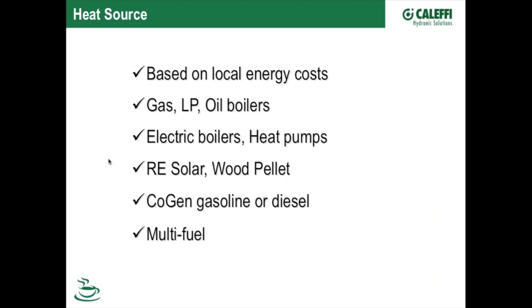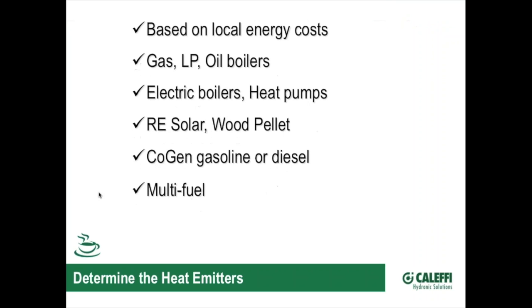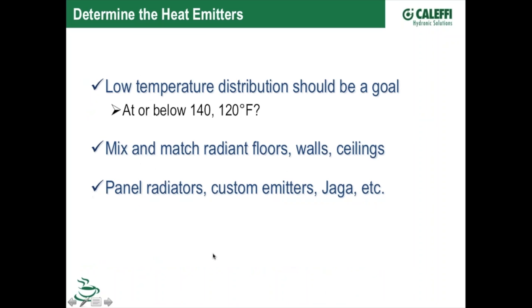You can compare the cost of operation for different types of fuel sources. There are calculators online. I think the DOE, Department of Energy, has a really good freebie calculator if you want to say, well, this is what I'm paying for gas or oil or LP or what my wood costs are, and you can compare it. And there are other different inputs. It could be a cogen unit, where you run the generator to provide power and pull heat off of that, or a combination of those. Multi-fueled systems use some sort of combination of all these things. We've got to bring them all together. We've got to make sure they all get along with one another for pumping requirements and everything else.